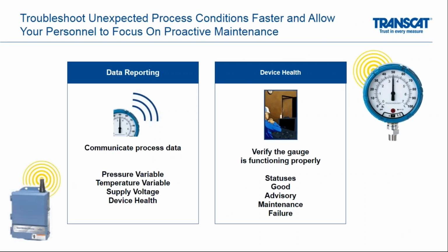There's a lot of different actions that you can take based on this. Certainly, the data can be reported using the WirelessHART protocol, using a gateway, similar to the gateway you might see on the bottom left here. You can communicate all of that device information from the wireless pressure gauge back to that gateway, back to a host system, and there's a ton of different variables that you can get as a result. The other piece is you can then verify that a gauge might be functioning properly without having to go out to the gauge to know that. All of that information can be sent wirelessly, it doesn't have to be, but if you use that kind of functionality, you now know all of the different variables, all the status, and if maintenance needs to be done, you know exactly which gauge maintenance has to be done to.